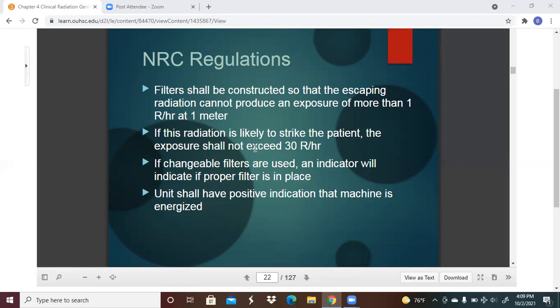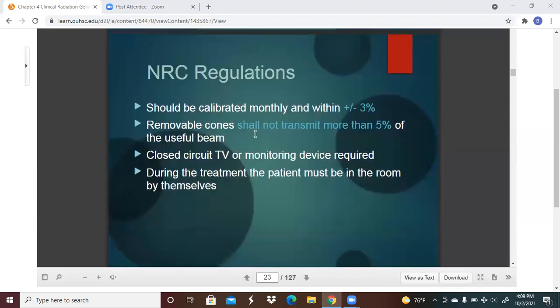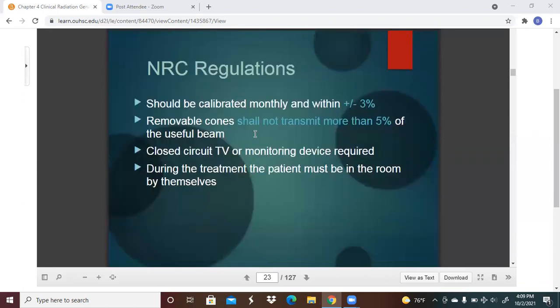If changeable filters are used, then an indicator will indicate if the proper filter is in place. And the unit shall have positive indication that the machine is energized. You have to calibrate it monthly. You've got removable cones that shouldn't transmit more than 5% of the useful beam. A closed circuit TV or monitoring device is required, and during the treatment, the patient must be in the room by themselves.